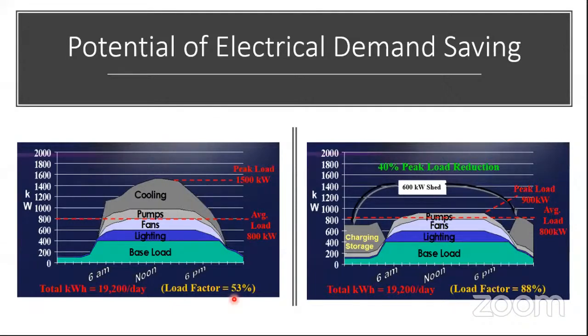Thermal energy storage gives us the option to have a lesser installed connected load and have our machines store the thermal energy in the hours when the load is less, let's say in the night hours. In these hours, if the connected load is nearly 900 kilowatt, because our building load profile remains the same, so with 800 kilowatt average load and 900 kilowatt as a connected load, the machines which we use for charging the thermal storage at night. So this gives us a far better load factor, that is 88% average load versus peak load, and we are still able to cater to the entire load.